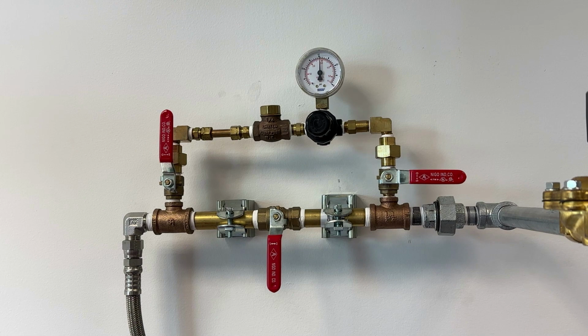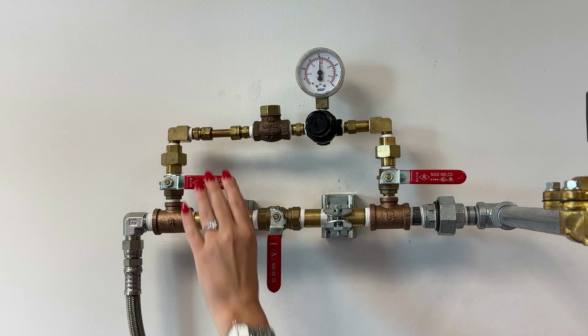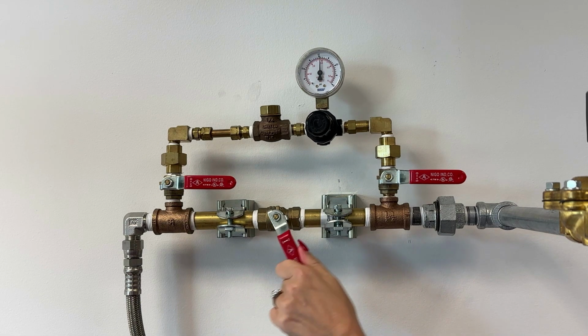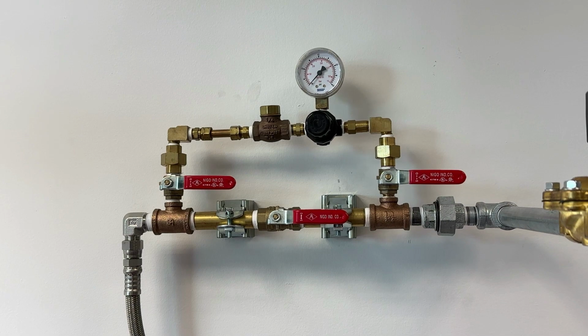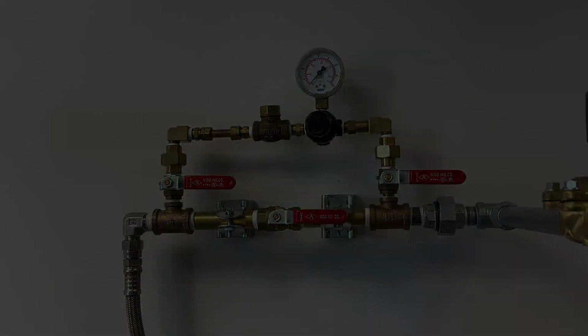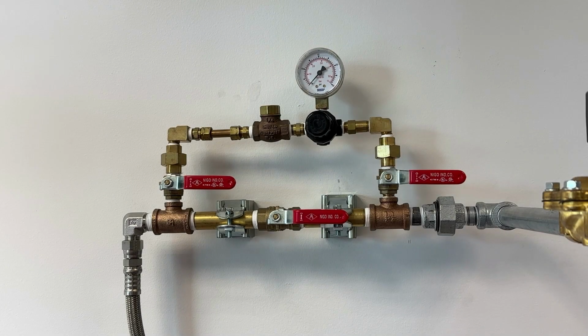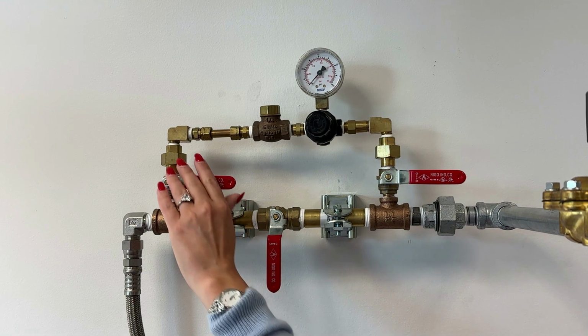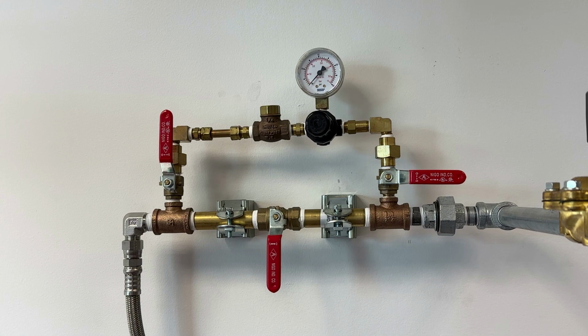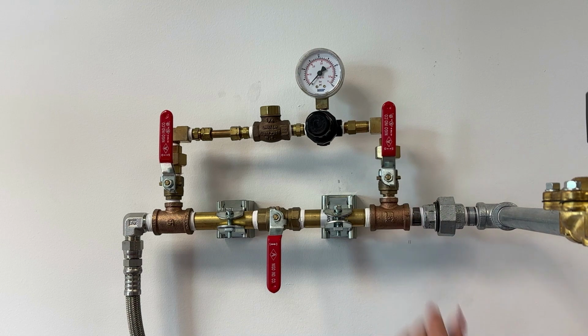Next, we need to fill the fire sprinkler system to its operational pressure. Begin by closing the inlet valve and opening the bypass valve. Observing the pressure gauge on the supply side of the sprinkler valve, fill the system to 5 psi below operating pressure. Once it reaches desired pressure, close the 1/2-inch bypass valve. Open the 1/4-inch regulator inlet ball valve and check to make sure regulator is set at desired sprinkler system pressure. Open the 1/4-inch regulator outlet ball valve and allow the sprinkler system to slowly pressurize to the desired operating pressure. The Potter Advanced Air Maintenance Device is now operational.